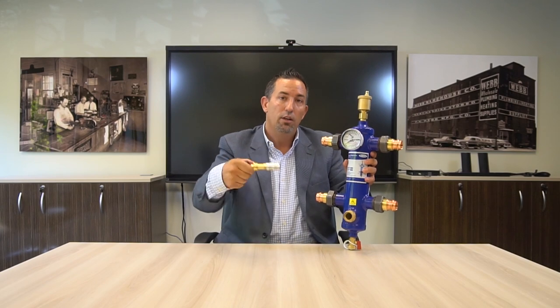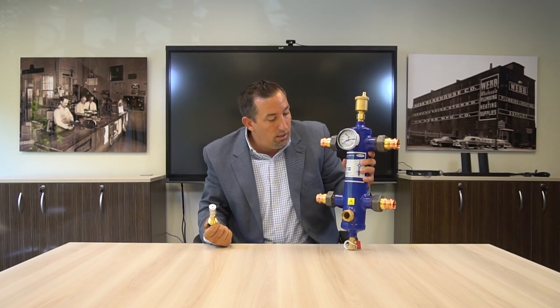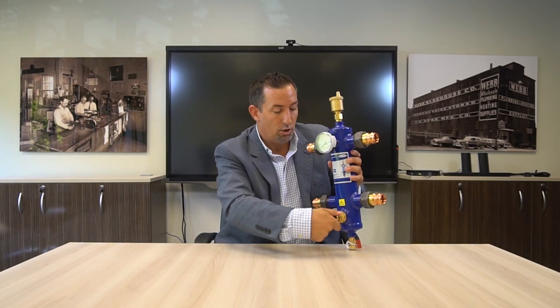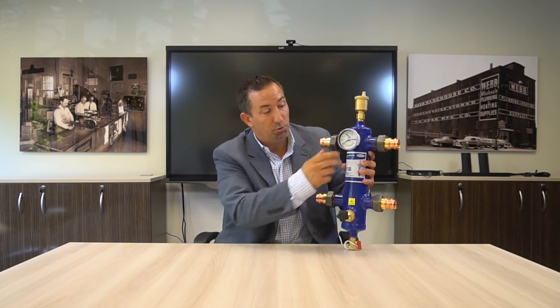Anybody's installing ECM pumps, you know that the magnet on an ECM pump, the motor, is magnetic. So if you're not removing that magnetite and those ferrous materials in your system somehow, there's only two places where it's going to collect. One of them is the heat exchanger, which happens to be the most expensive part of the boiler or combi. And the other place it could be is your system pumps, right? And you could be replacing circulator pumps in a very short period of time. So very important to get those ferrous materials out of the system, that magnetite. And obviously you want to know what your temperature and pressure reading is in the system, so we have this built-in tridicator. All of this comes with this unit.